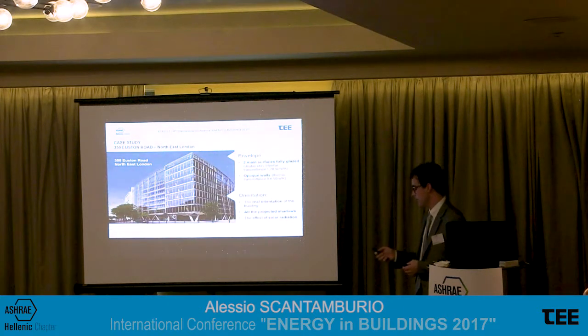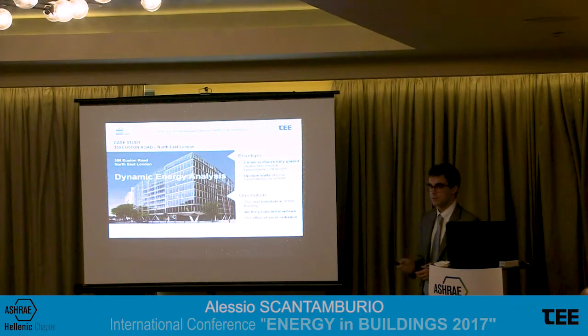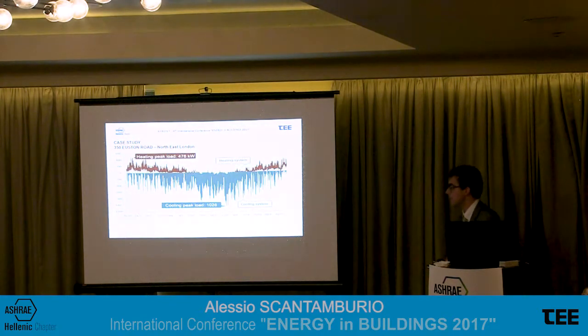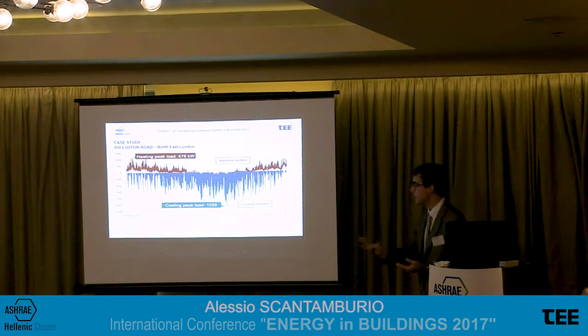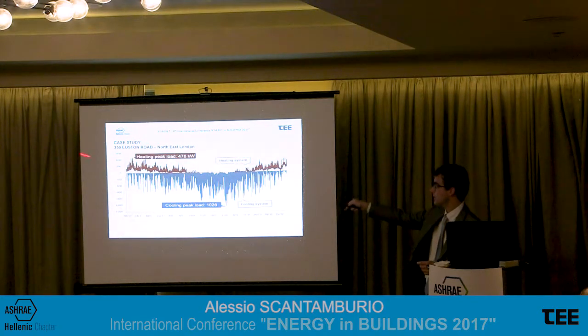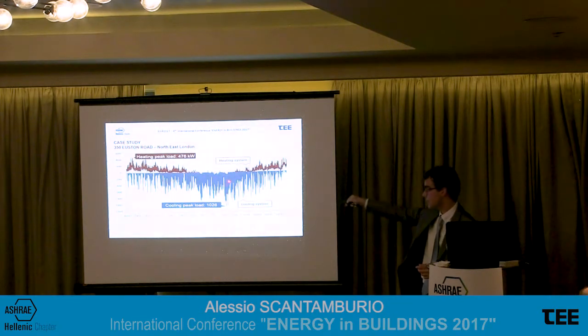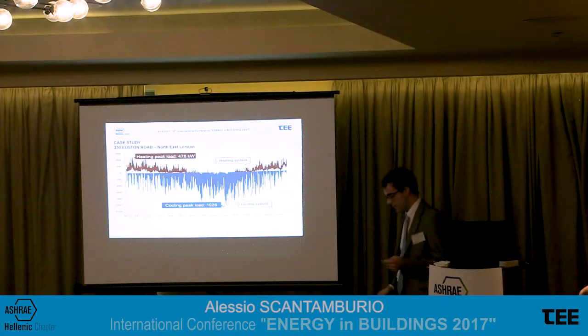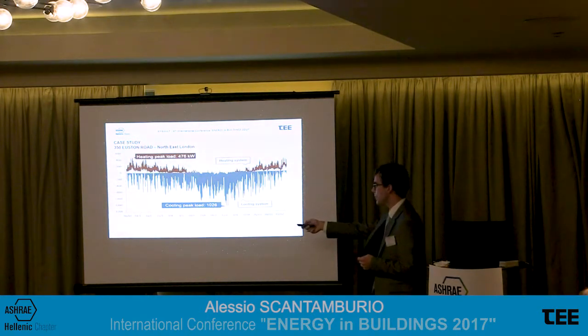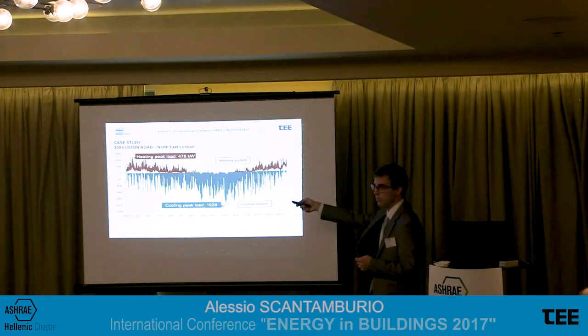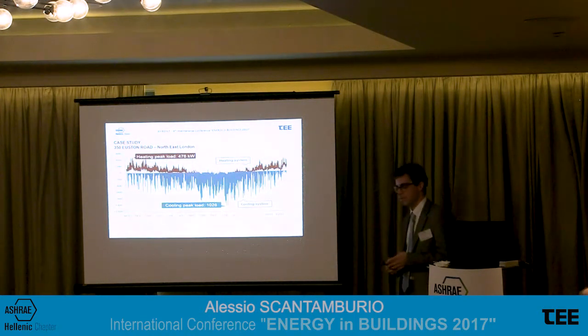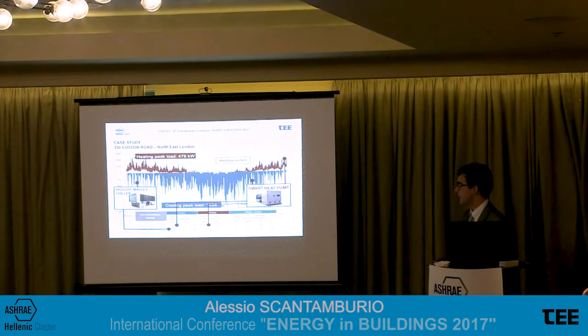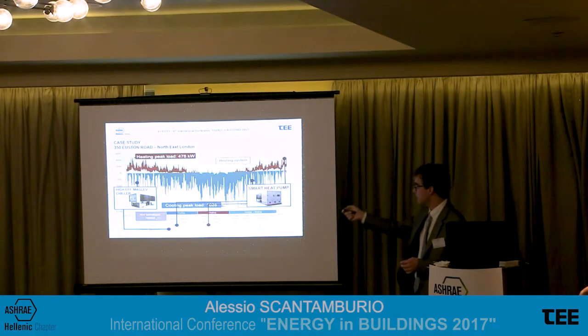people inside. Okay, and so we carried out a dynamic energy analysis, and we found that this is actually the thermal profile of the building over a 1 year period. So for most of the time you see that this particular building requires heating and cooling at the same time. Only for a few months during the summer the building is requiring only cooling. In particular, this is another interesting point, that as you can see, the cooling peak load is more or less double the heating peak load. So what was the best combination between units? Well, the result has been selecting a smart heat pump, a 4-pipe unit covering the maximum heating peak load.